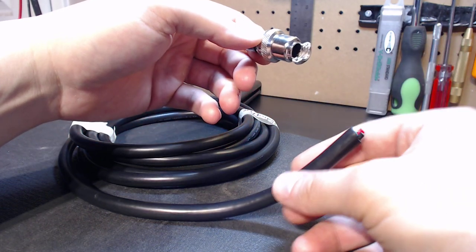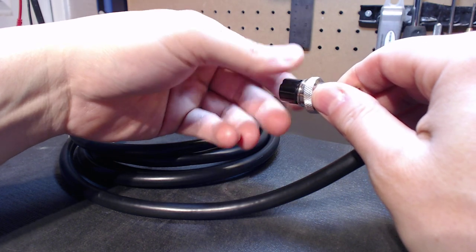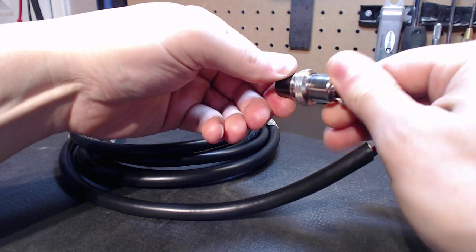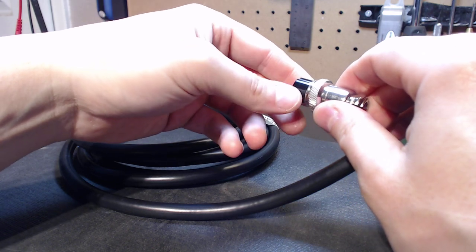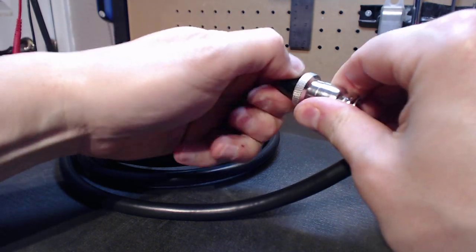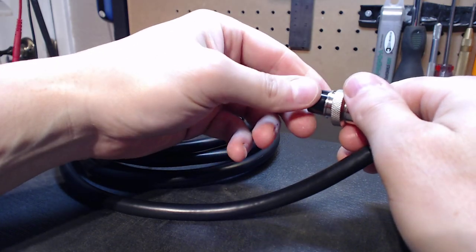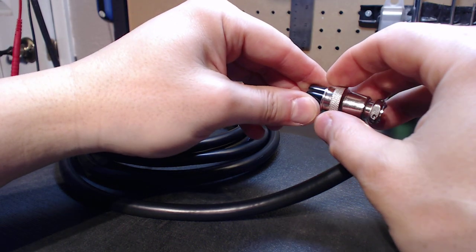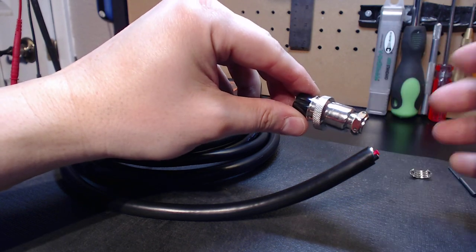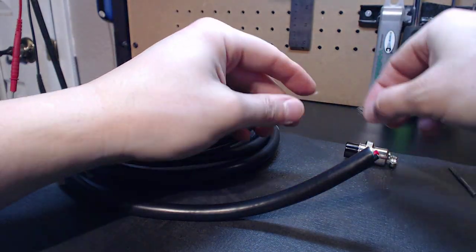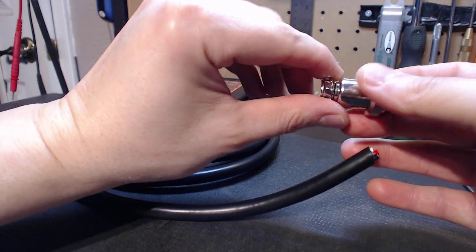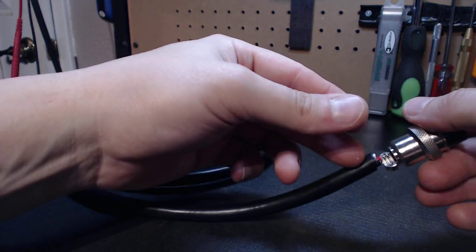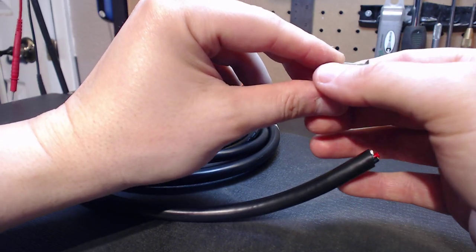You want to make sure that when you open this unit up that you deburr everything. The metal casing has to be opened. It has to be deburred so you're not scratching the piss out of your casing on your cable. You want to rotate this until it locks. That's what we're trying to do. Because once the cables leads are actually connected here, you will not be able to spin the cable so easily. Always take into account where you're going to cut your casing off because you are going to have an engagement of your actual stress relief. Your stress relief has to come in here and make contact with the outer casing.